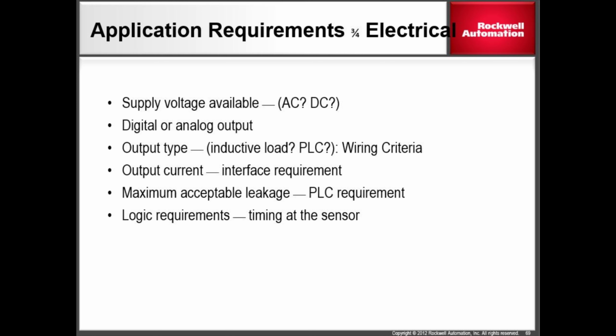Am I sending a signal to a PLC? Am I turning on a light? Am I moving a conveyor? What am I doing with that signal? How much output current do I need? Most of these sensors typically are electronic devices, so it's in the hundreds of milliamps that the output current they can handle. So you've got to consider that. I might have to interface it with a relay if I'm hard wiring like that. If I'm going to a PLC, I might have to have a relay output on my PLC depending on how much current I'm trying to control.